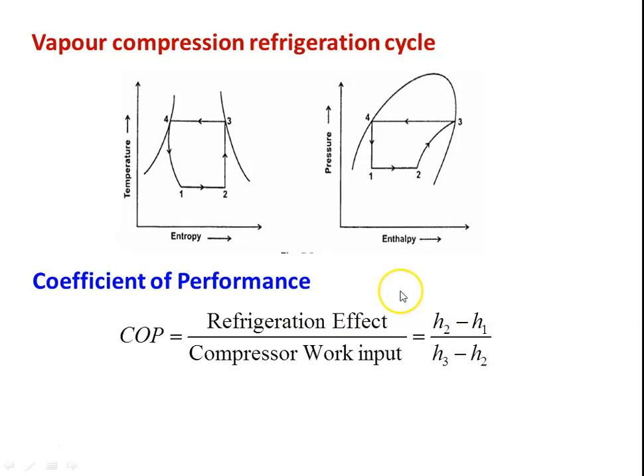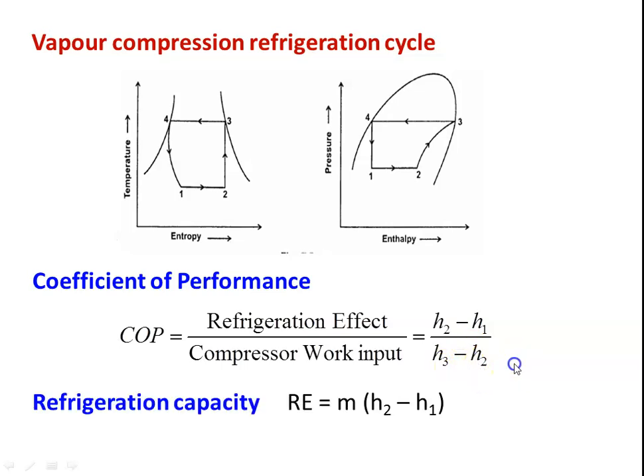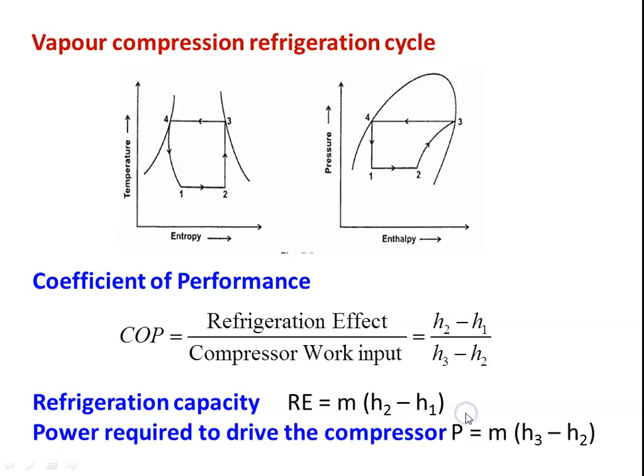The coefficient of performance is defined as refrigeration effect divided by the compressor work input. Refrigeration effect is the enthalpy difference across the evaporator; compressor work input is the enthalpy difference across the compressor. So COP = (H2 - H1) / (H3 - H2). Refrigeration capacity Re = M × enthalpy difference across the evaporator. Power required to drive the compressor P = M × enthalpy difference across the compressor.